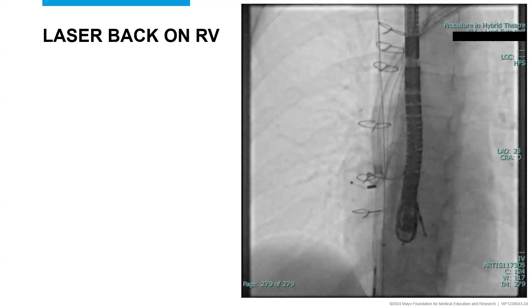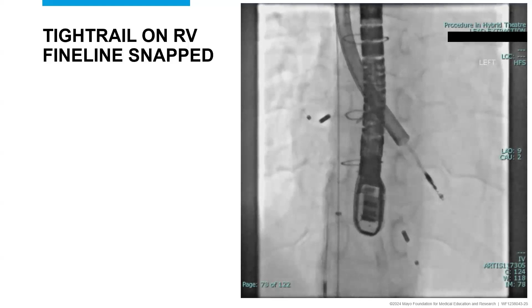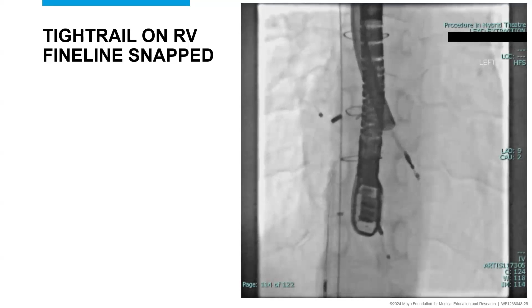And now again, unfortunately, we missed another bit on our stepping, because if we press our foot back on the pedal too quickly, it goes. But you can see in the middle there, the TightRail, the FineLine tip is sitting on its own, and it's snapped at this point. I'll just show you an image about that in a minute. And we're back onto the 2004 active fixation lead. We don't know the details of this lead. We're just trying to work it down with the TightRail, and we're up to a 13 TightRail at this point, the largest inner diameter that we've got, to try and get right down to the tip here.